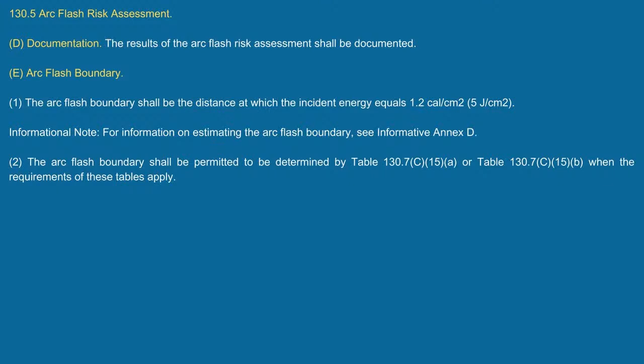Yeah, you always have to evaluate the fault current. If you don't know that, then you don't know what you're going to need. You're going to need the clearing time in order to use the tables, and you can't exceed the parameters that are listed underneath the table. If you do that, then all of a sudden the table is no longer valid. And we're going to look at that next week. We're going to go more in depth on that. And I'm actually going to make up a problem and go through it and show you how you do it both ways. Okay.